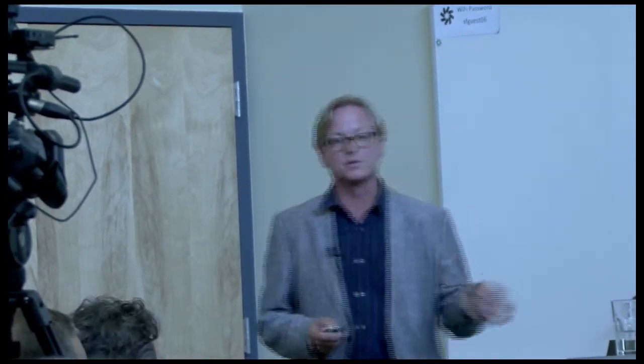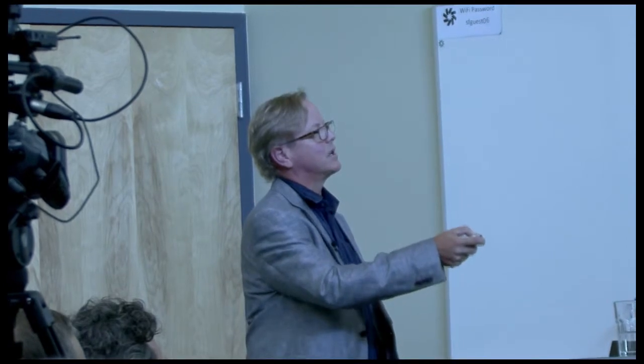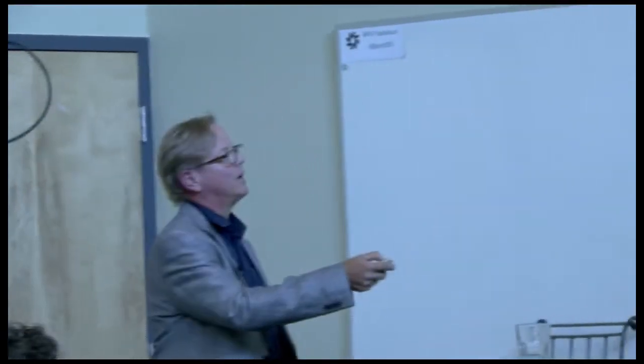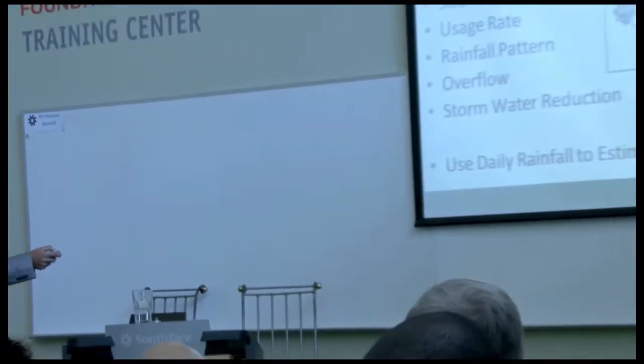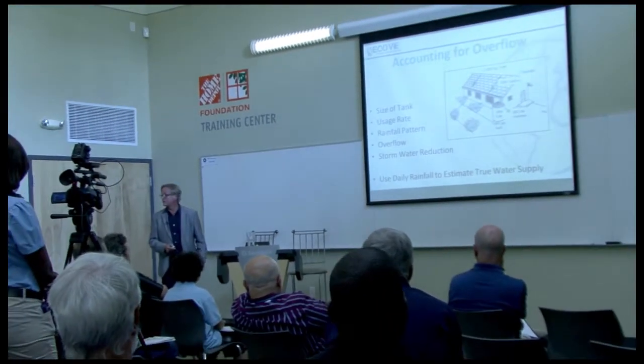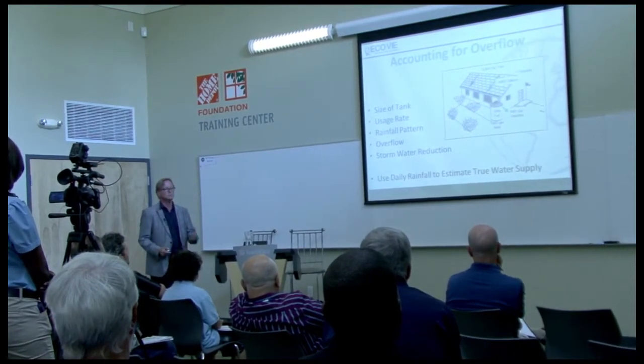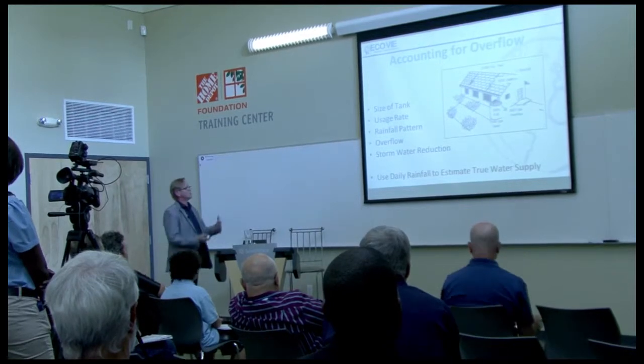So that doesn't really tell you how much stormwater you're mitigating. It doesn't really tell you how much water you're supplying. But what you do need to know is how much your tank is overflowing and how much you're using. So say, take any rooftop, let's say it's 2,000 square feet, an inch of rain falls, about 1,060 gallons makes its way into the tank. Your tank is already half full. That means 660 gallons is going to overflow. So you need to deal with that with your bioswale or whatever.